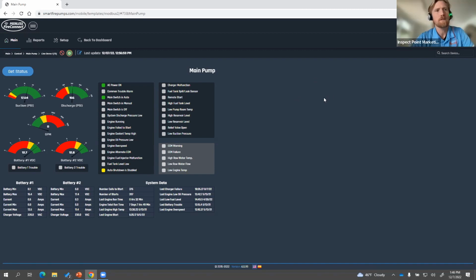Obviously, on the annual, that's not going away anytime soon, if ever. But for those churn tests and no flow tests, there's some neat stuff coming. Especially by being able to crunch this data now that it's available, we can make more informed decisions in terms of what we actually need to look for. What is actually an issue versus what is something maybe somebody thought a while back was an issue, so they put it on a checklist, for example. We can start to look at what those failure points are.